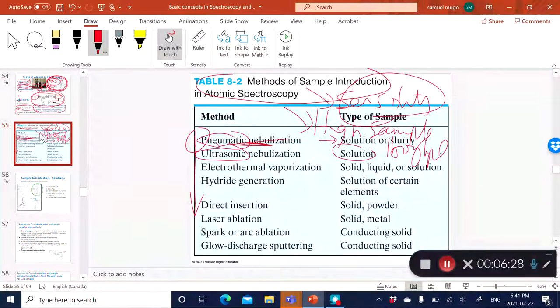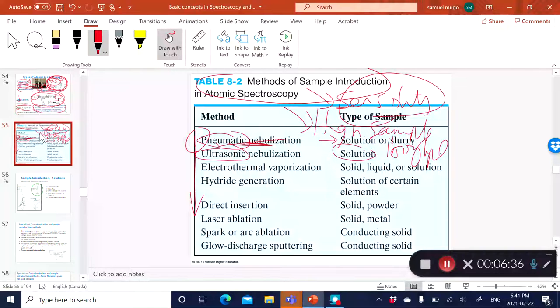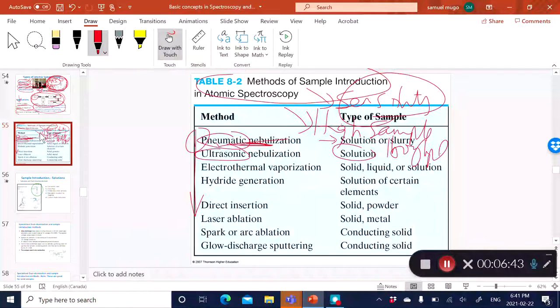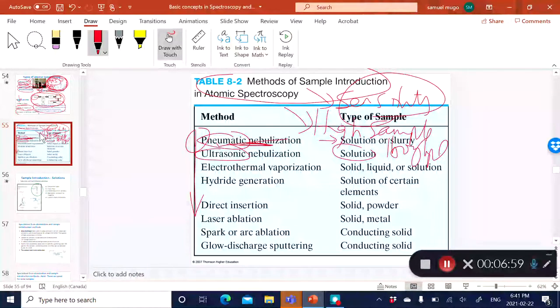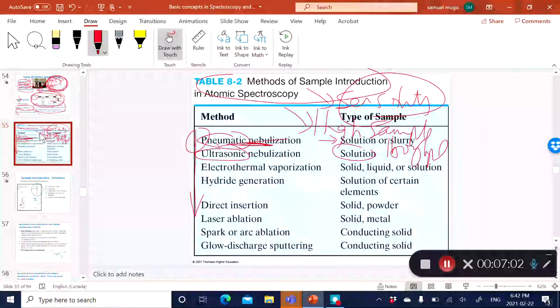Another method is ultrasonic nebulization. In this process, you introduce a solution and the solution impinges on a crystal that is vibrating. Because the crystal is vibrating, the solution splits into a mist. Ideally, you want the sample to be converted into a mist that is transferred into your atomizer.